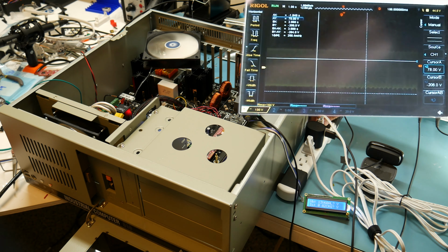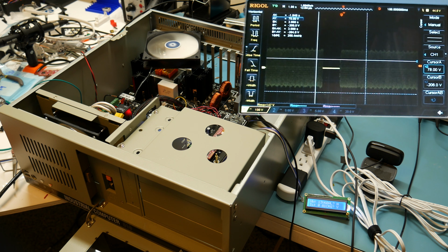After many power cycles, I managed to flip the power strip in sync with the peak of a sine wave, and this tripped the overcurrent protection due to the inrush current into the 2 LED light bulbs and the phone charger. Notice how there's a couple seconds of off time right after we flip this on and trip the current limit?